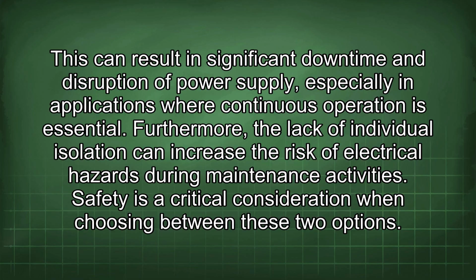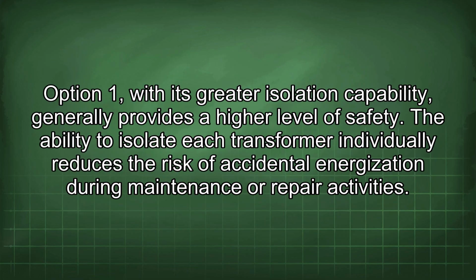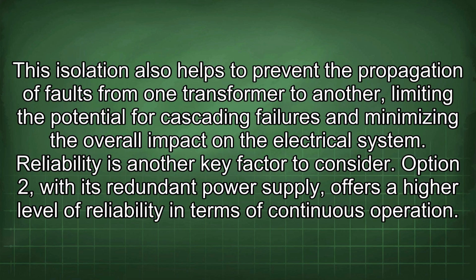Safety is a critical consideration when choosing between these two options. Option 1, with its greater isolation capability, generally provides a higher level of safety. The ability to isolate each transformer individually reduces the risk of accidental energization during maintenance or repair activities. This isolation also helps to prevent the propagation of faults from one transformer to another, limiting the potential for cascading failures and minimizing the overall impact on the electrical system.